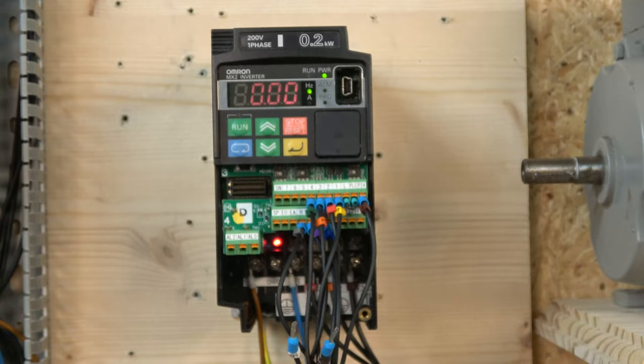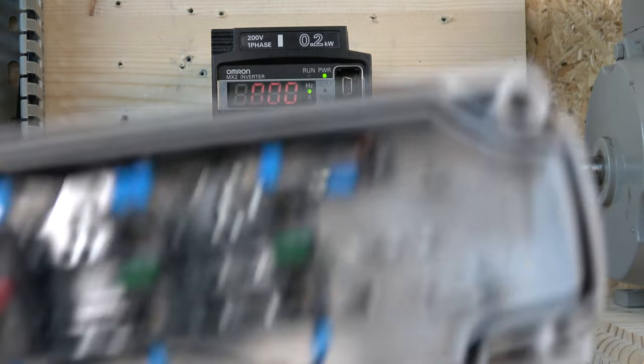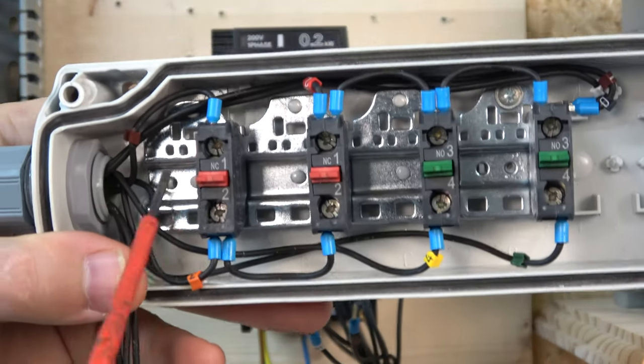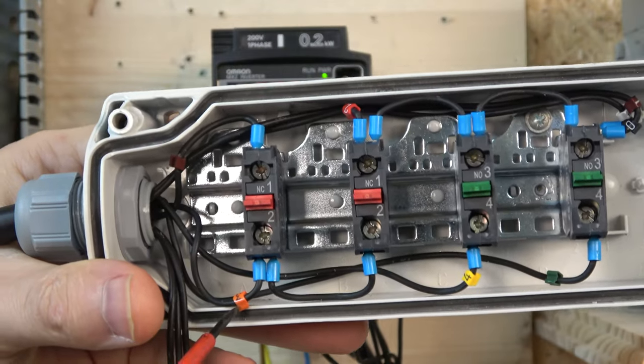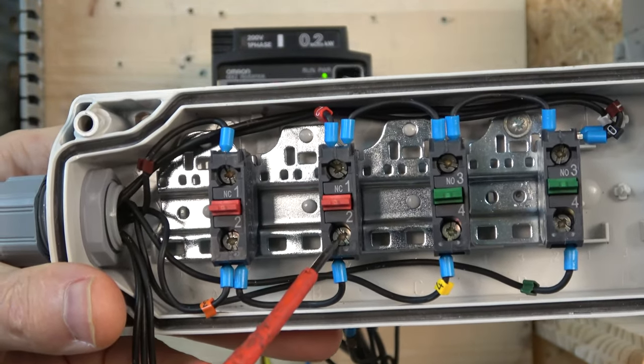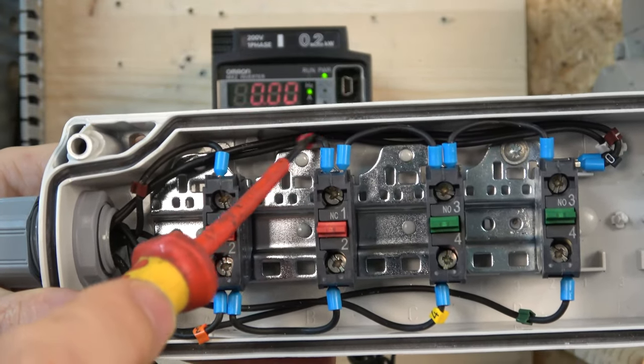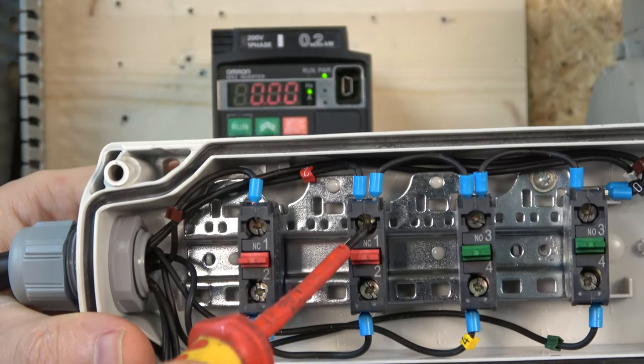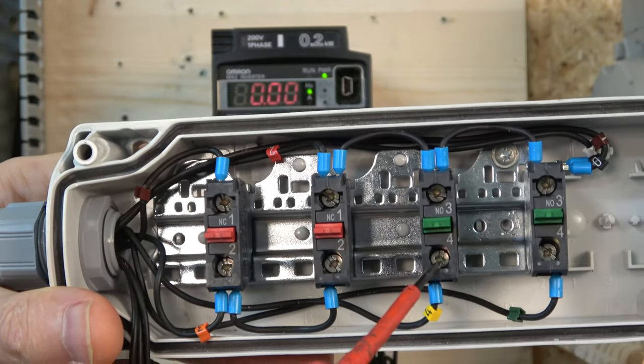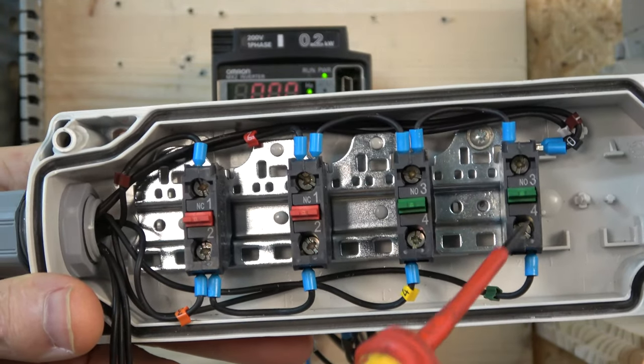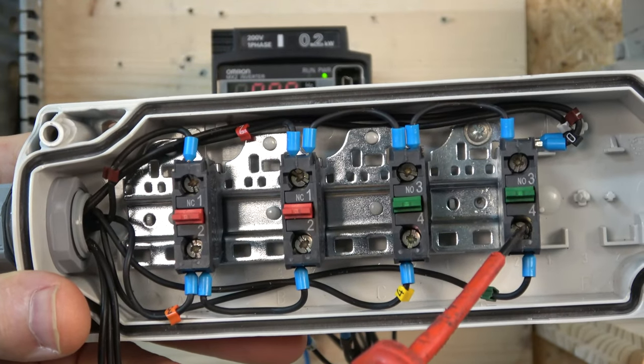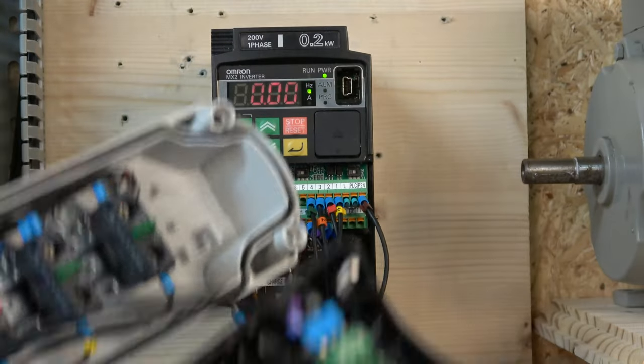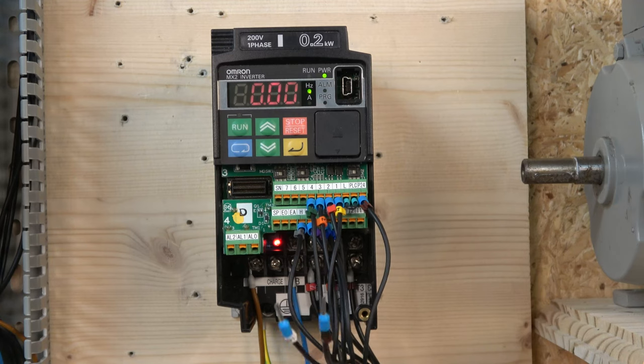Wiring wise, what we've got in here is we have again our normally closed contact which is our e-stop sending a signal back to terminal 3, and also going to another normally closed contact which comes through. They're sending back another cable after the normally closed contact for the stop button. That one's going to go back to terminal 2. Then terminal 1 is going to be the start button, and terminal 4, this guy here which is leaving here, that's going to be our selection between forward and reverse. And then obviously we have a potentiometer which is still very much the same as was before.